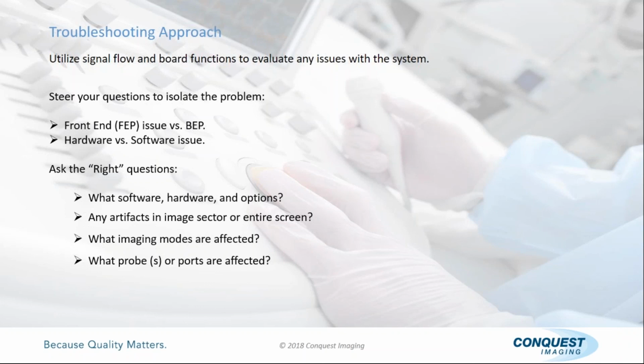What imaging modes? Is it color? Is it Doppler? Is it 2D only? You want to know which ones are affected. Multiple probes and multiple ports. One of the most fundamental things you ask in ultrasound. This only has a single port, but most of them have 3 ports or 4 ports. So is this artifact that you're seeing in the image area affected by multiple probes in multiple different ports? That helps you isolate it.